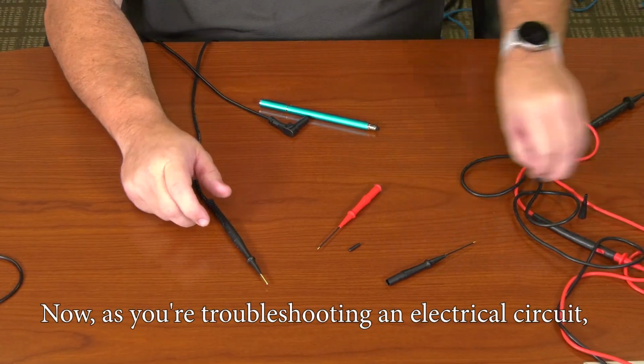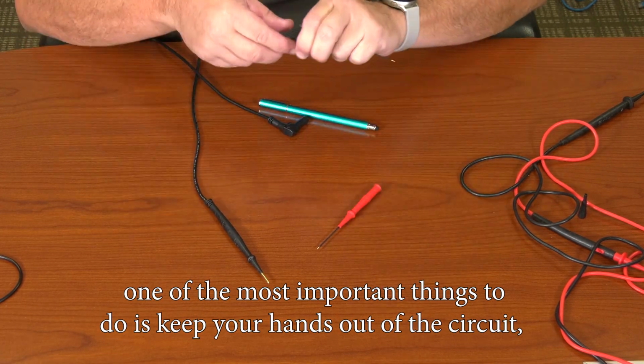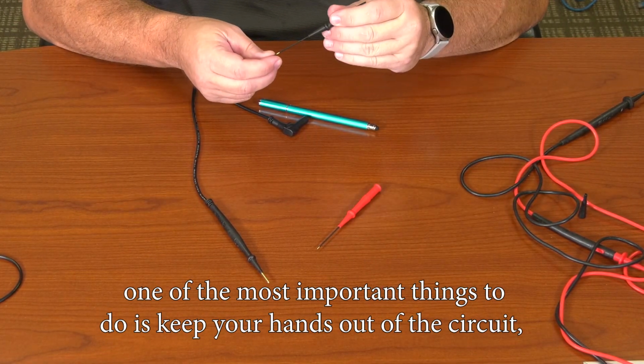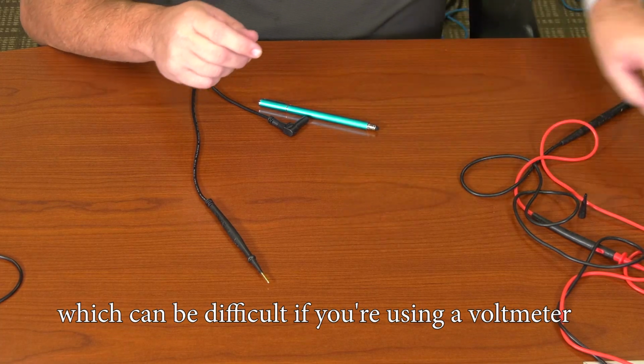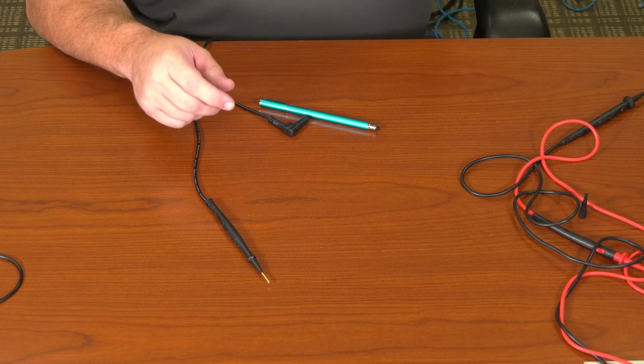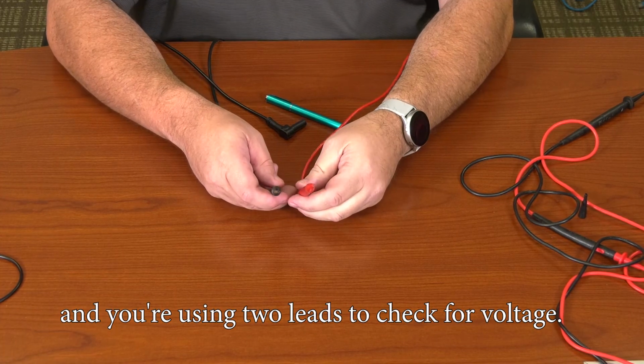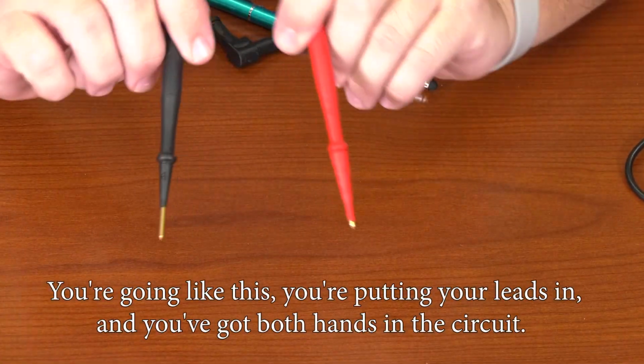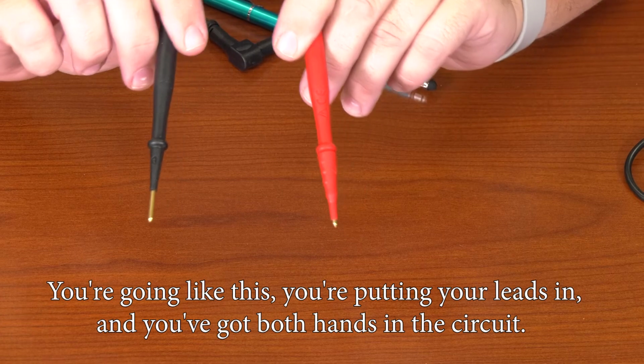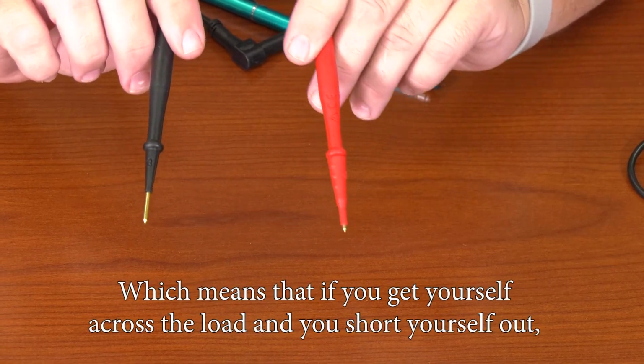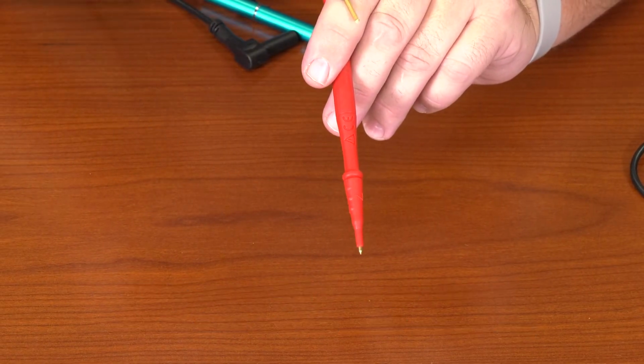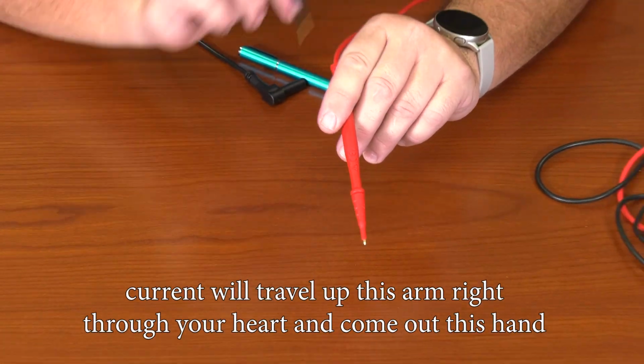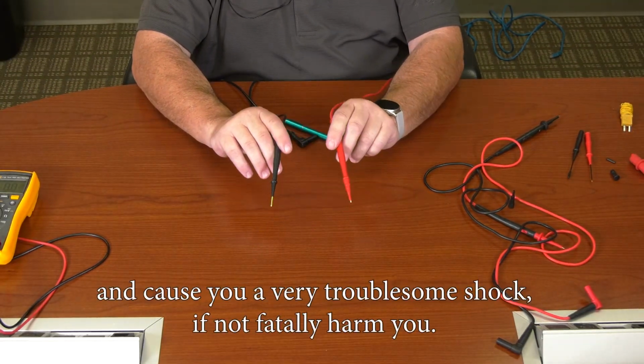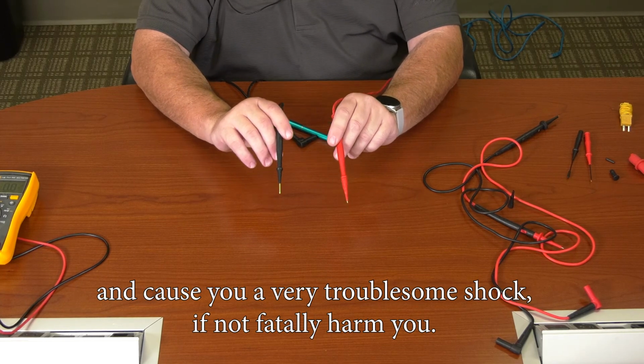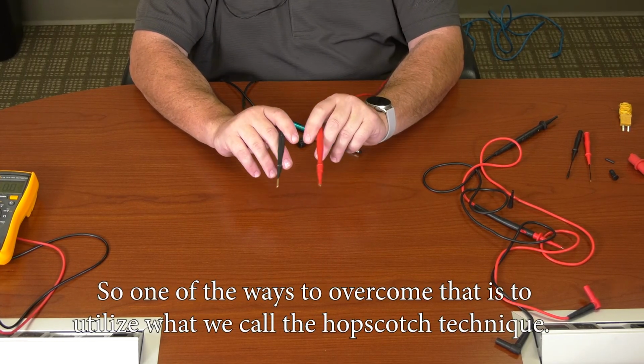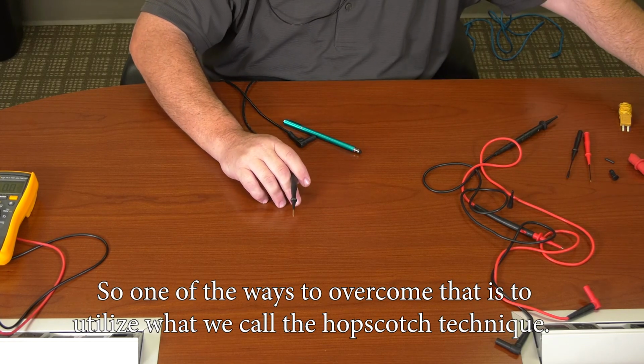Now, as you're troubleshooting an electrical circuit, one of the most important things to do is keep your hands out of the circuit, which can be difficult if you're using a voltmeter and you're using two leads to check for voltage. You're going like this, you're putting your leads in and you've got both hands in the circuit, which means that if you get yourself across the load and you short yourself out, current will travel up this arm, right through your heart, and come out this hand and cause you a very troublesome shock, if not fatally harm you. So one of the ways to overcome that is to utilize what we call the hopscotch technique.